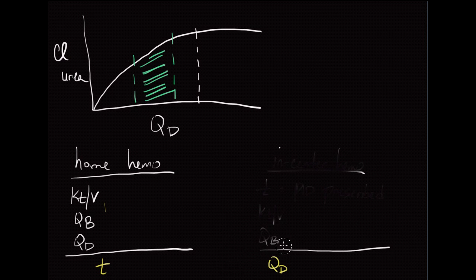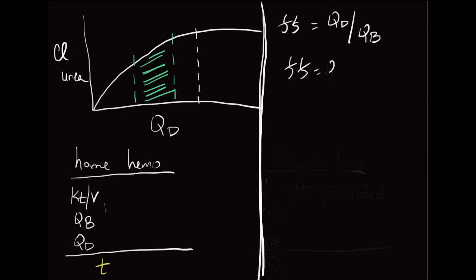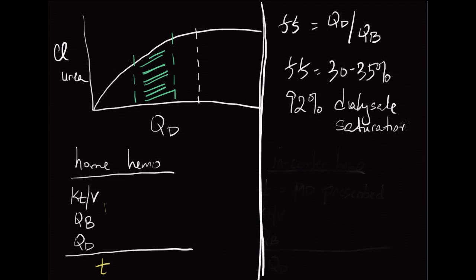Let's look at the flow fraction in more detail. The flow fraction is a very straightforward formula — denoted FF — and it's the ratio of the dialysate flow rate over the blood flow rate. What we want in a home hemo patient is a flow fraction of about 30 to 35%. The reason for this number is that a dialysate-to-blood flow ratio of 30 to 35% yields about 92% dialysate saturation of urea — meaning you get very high urea clearance for the least amount of dialysate flow. This is something prescribed by the physician.